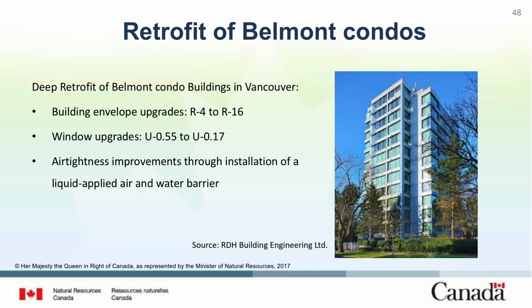Finally, air tightness improvements were made to the enclosure through installation of a liquid-applied air and water barrier over cracks in the concrete. The whole building air tightness was tested before and after the retrofit. The initial pre-retrofit air tightness was 7.6 CFM per square meter at 75 pascals. Following the retrofit, the air tightness dropped to 3.5 CFM per square meter at 75 pascals.